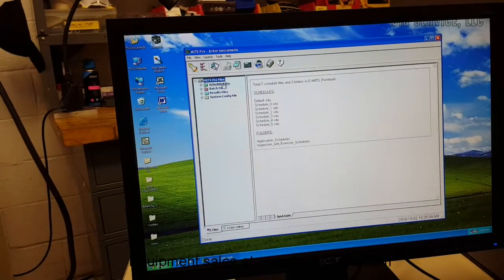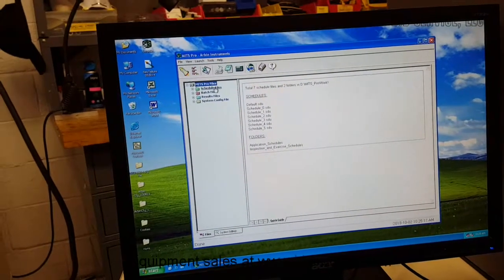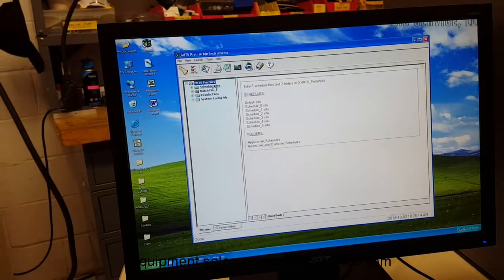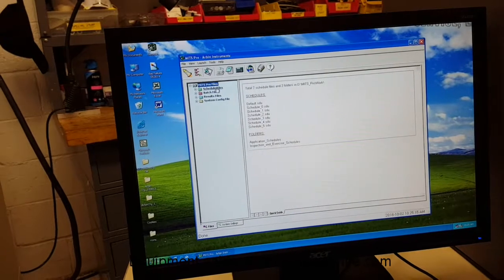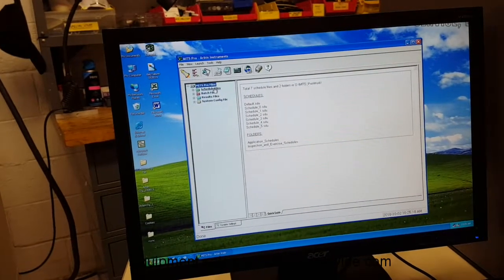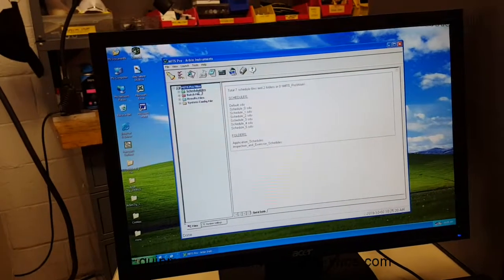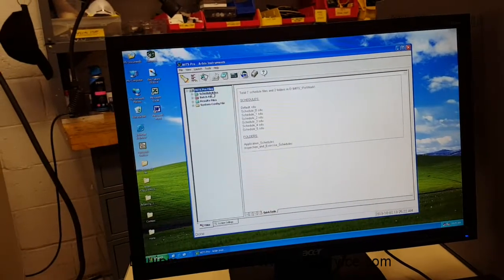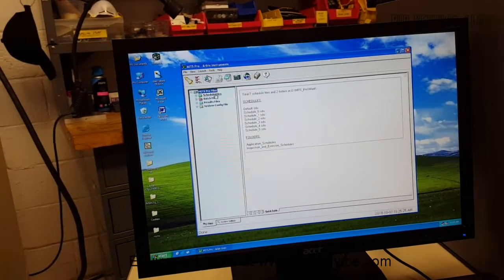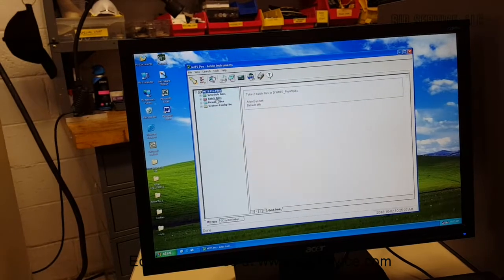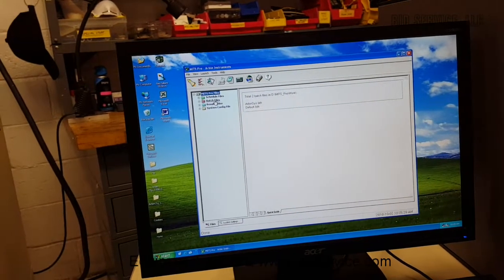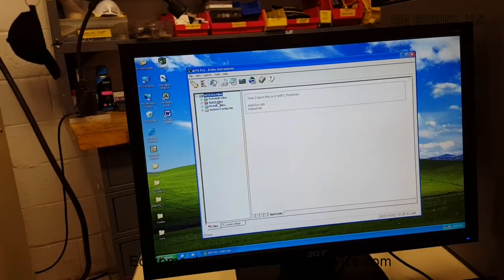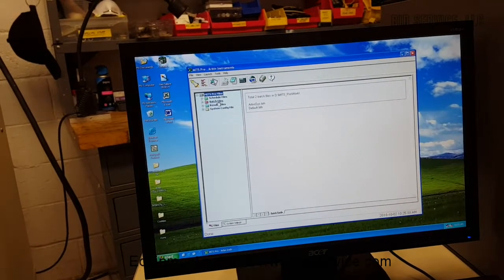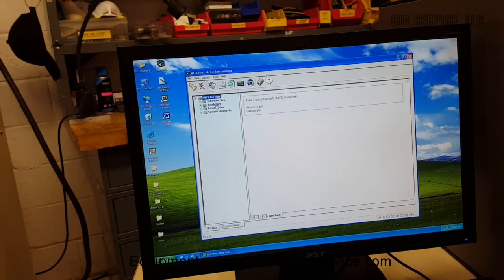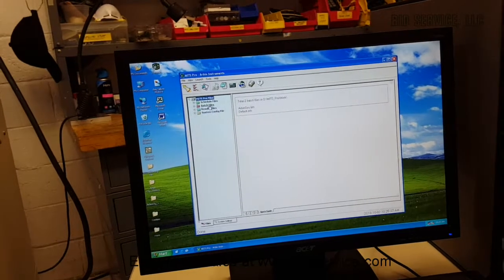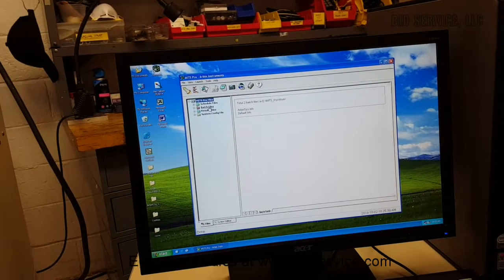From the main screen here, we're going to go through each of the main routine steps. Schedule files. Schedule files are your actual programs. This is where you would enter the values that you want to test, whether that be a range of current, a range of voltage or power. Next are the batch files. The batch files are what actually runs your program files or your schedule files. It allows you to assign your program to different channels and make different measurements.